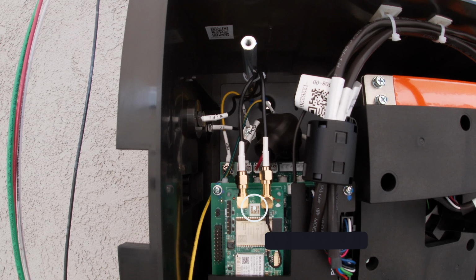And then you can have that solar connection up to 100 amps, or the EV charger, or secondary generator. Now you don't have to, if you did this as a DC coupled solution, because this is a hybrid inverter, so you can do AC coupled or DC coupling.